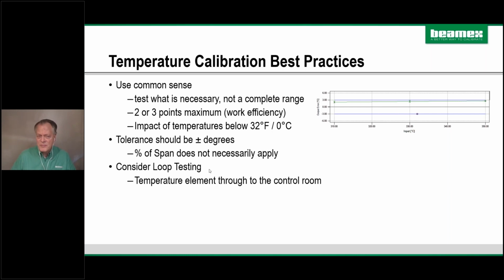Also, in best practices, people disconnect the RTD, simulate resistance into a transmitter, and check the 4 to 20. You're leaving out the most important component in the temperature measurement. So we like to encourage people to consider doing loop testing. Loop testing takes more time, but if you're doing an end-to-end test where you're dropping the sensor into a dry block or bath and then checking the readout in the control room, that's to me the best way to check a temperature, because you're making decisions in the control room based on that readout, and you want a true temperature displayed in the control room. It doesn't matter what's going on in between.